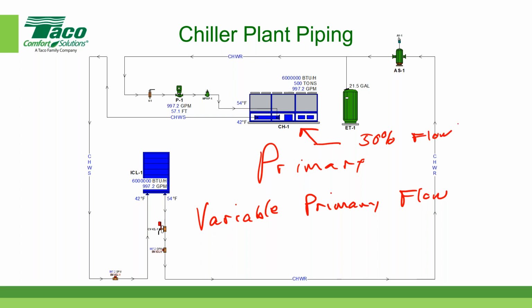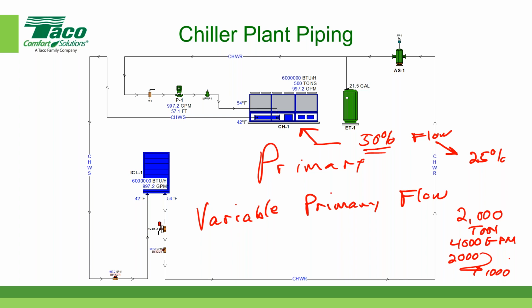And then if you use multiple chillers, in this case, it's only 1 chiller. If I use 2 chillers and each chiller was sized for 50% of capacity, then that means my flow in terms of the system could go down to 25%. So again, let's assume that I had a 2,000 ton system, just to put things in perspective, 2,000 tons, and if I had a 12-degree delta T, that would be 4,000 GPM. And if I had 2 chillers, then each chiller would be 2,000. And if each chiller could go down to 50% flow, that would be this value here, then that means it could go down to 1,000 GPM. And 1,000 divided by the total of 4,000 is now 25%. So the more chillers that you use in a variable primary flow, the greater the variation in flow.